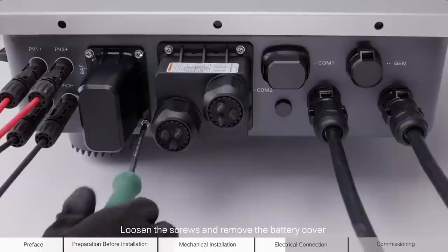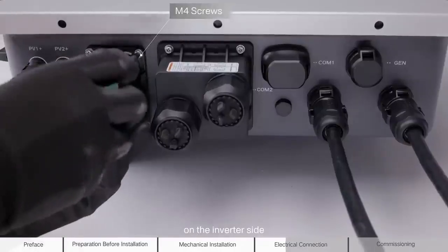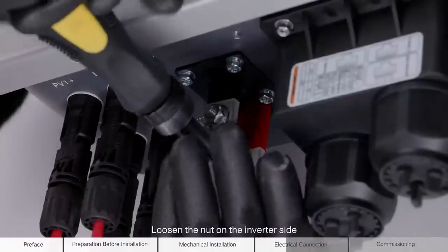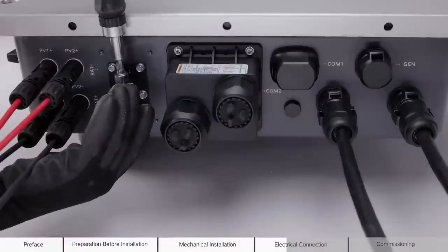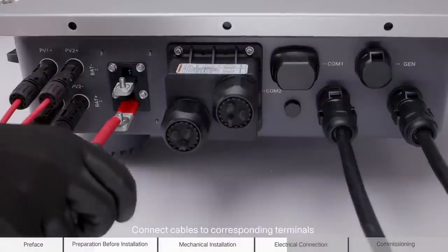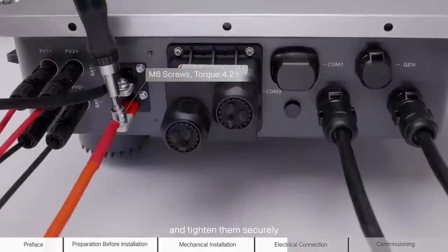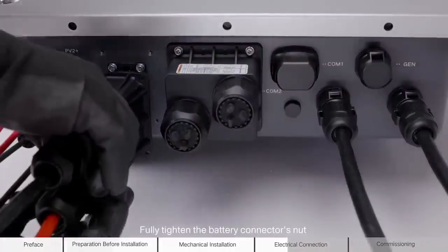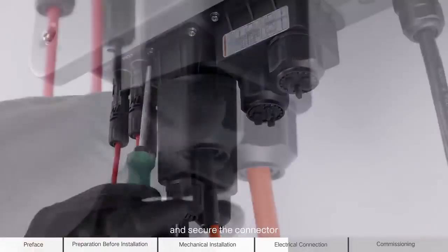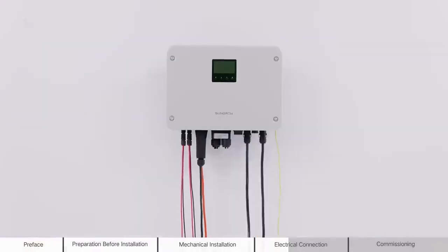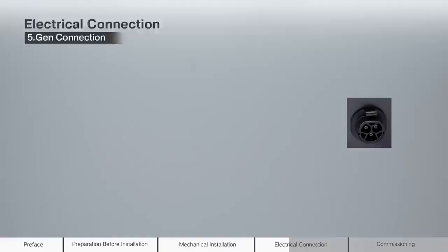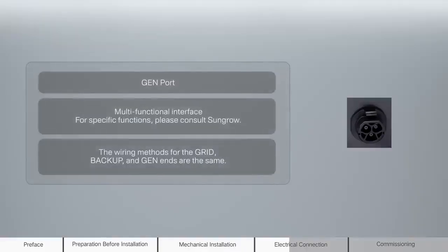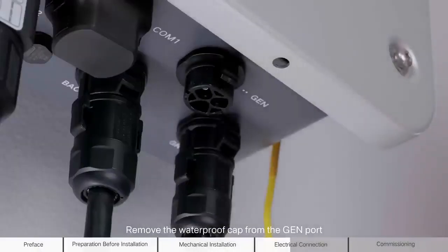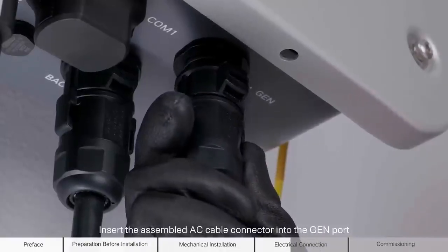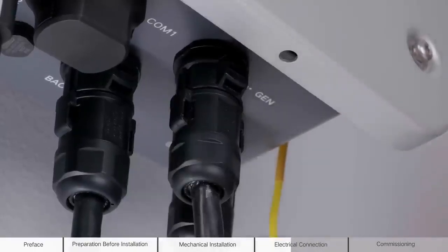Loosen the screws and remove the battery cover on the inverter side. Loosen the nut on the inverter side. Connect cables to corresponding terminals and tighten them securely. Fully tighten the battery connector's nut and secure the connector. 5. Gen connection. Remove the waterproof cap from the gen port. Insert the assembled AC cable connector into the gen port.